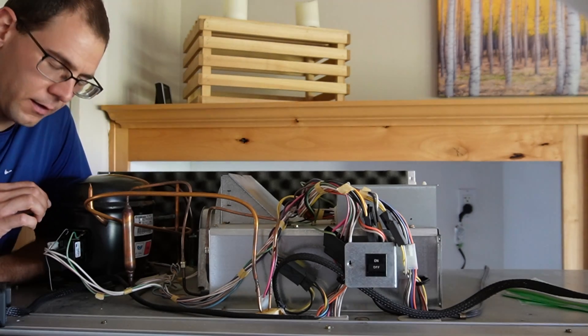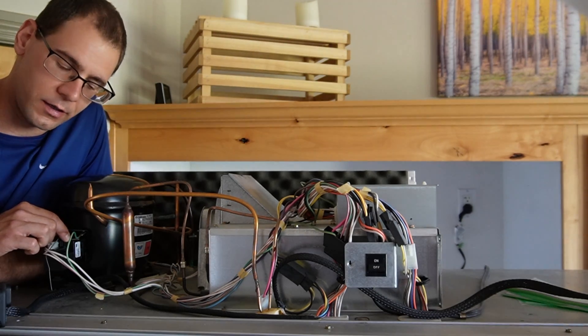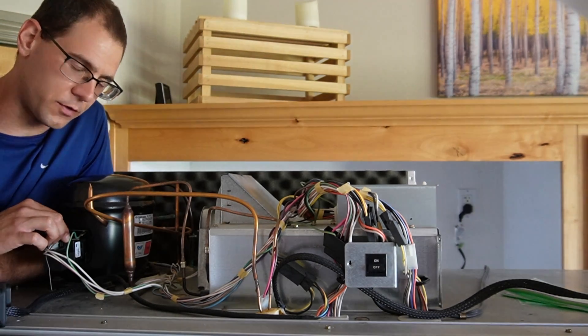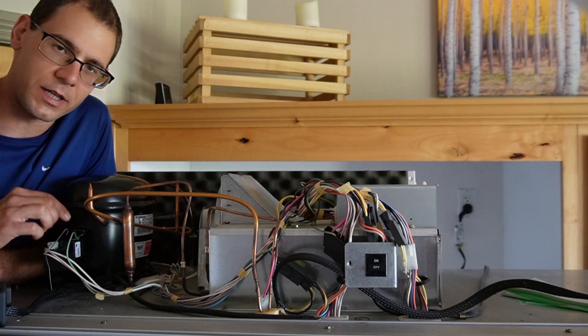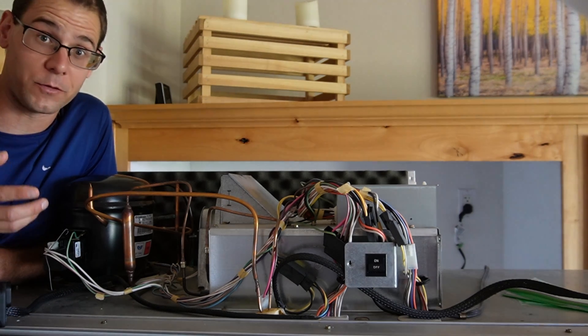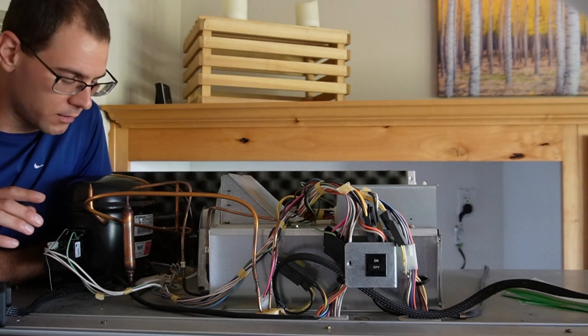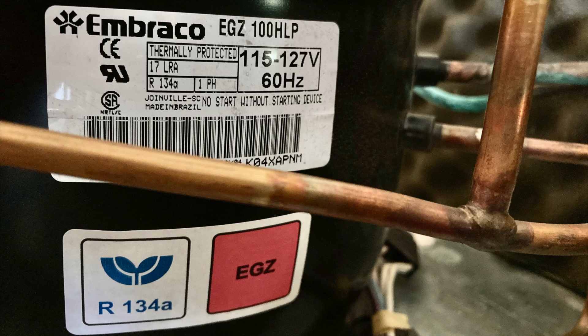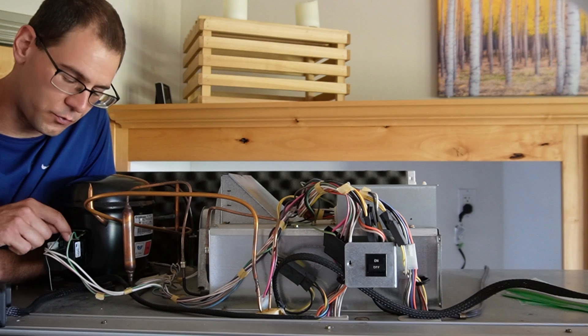I've looked at this in more detail and I think there's a very good chance it may have something to do with the relay which is right here, and on top of the relay we have a run capacitor. This relay is responsible for turning the compressor on and off. I really hope it's the problem because this can be replaced fairly easily, whereas if there's something wrong internally or with the refrigerant that would be much more difficult. I want to pull up a schematic based on the model number on this sticker and look at it in detail.